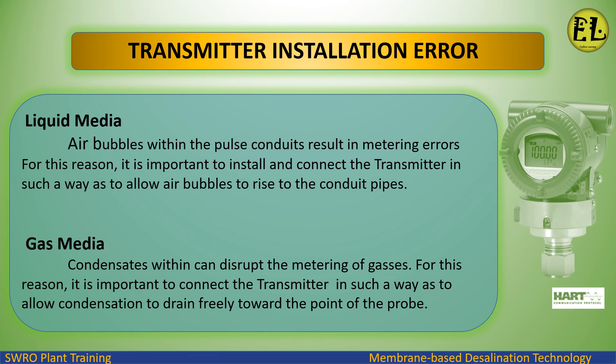Transmitter Installation Errors — Liquid Media: Air bubbles within the pulse conduits result in metering errors. For this reason, it is important to install and connect the transmitter in such a way as to allow air bubbles to rise to the conduit pipes. Gas Media: Condensates within can disrupt the metering of gases. For this reason, it is important to connect the transmitter in such a way as to allow condensation to drain freely toward the point of the probe.